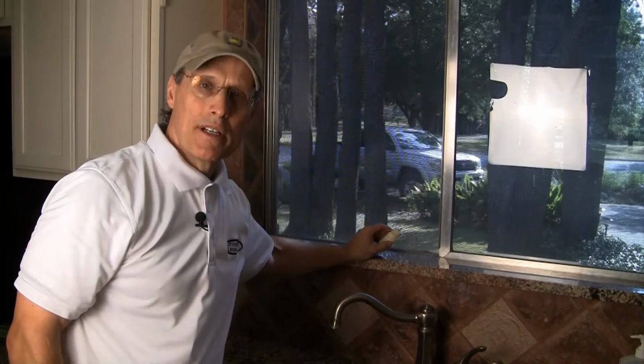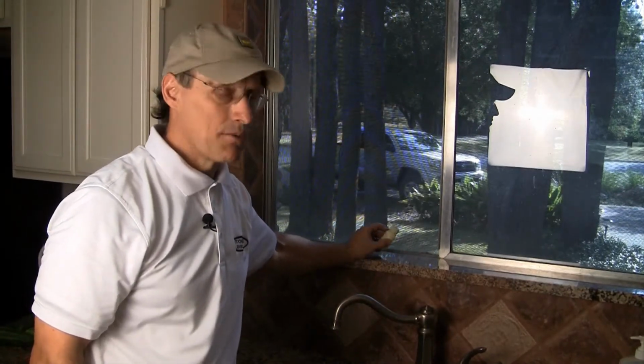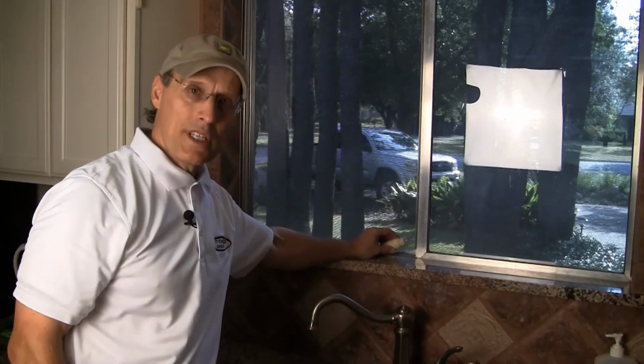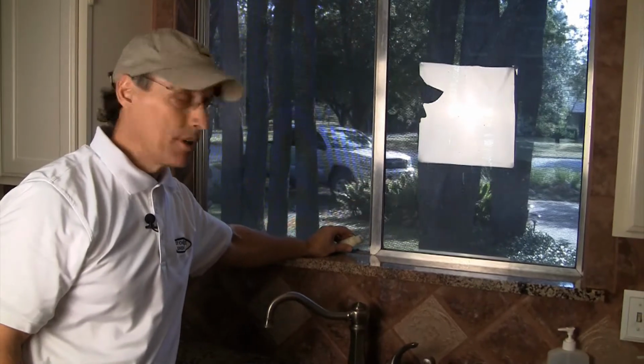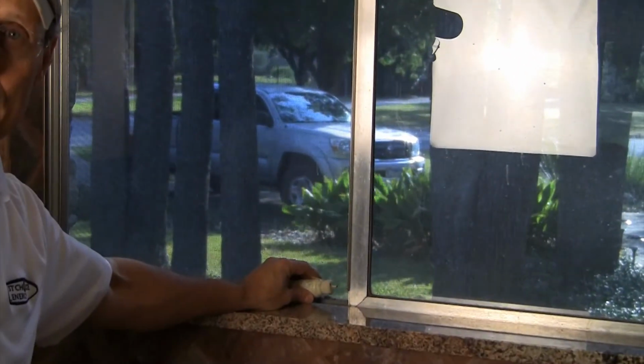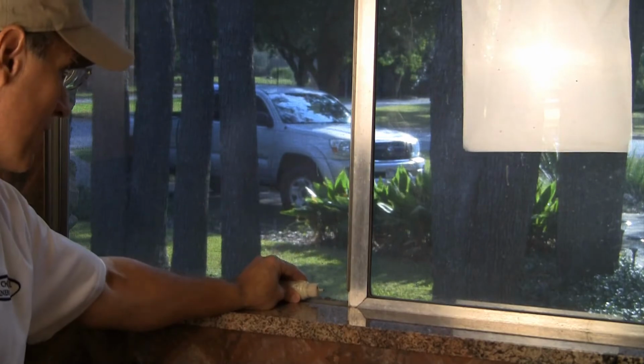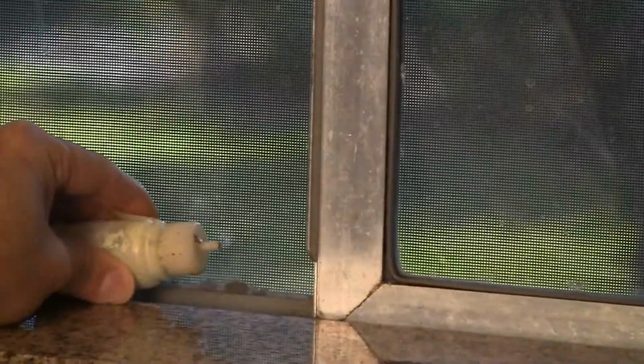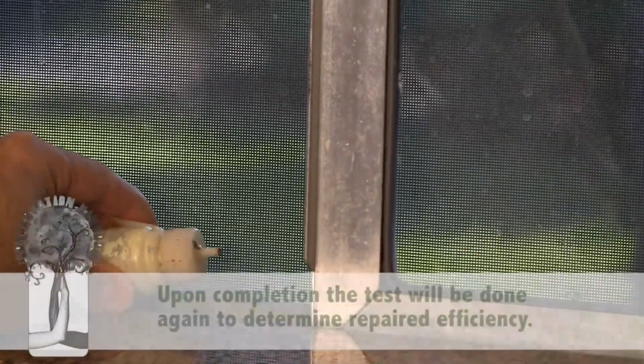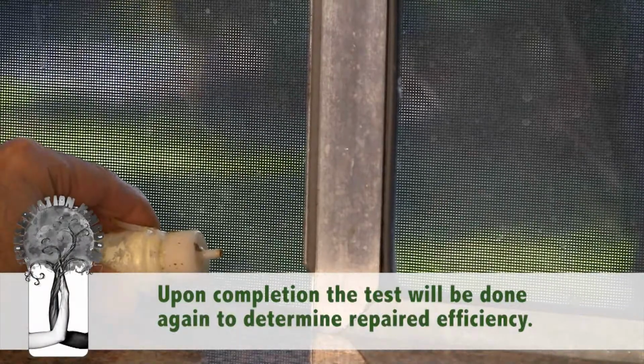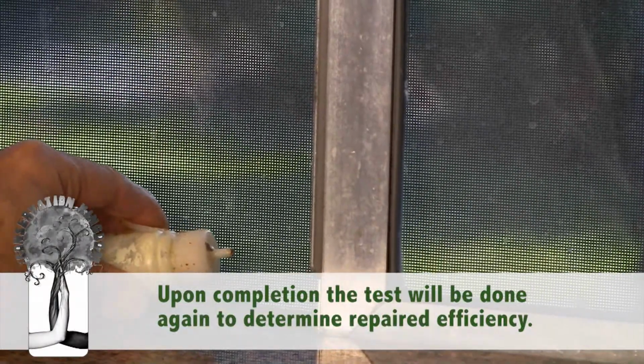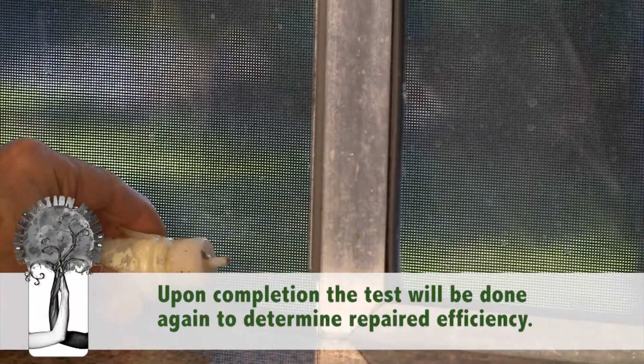Another common area of air infiltration into a house is around leaky windows. And so you'll see these are single pane aluminum frame windows, about 30 years old, 40 years old. And you can see if I puff smoke, I'm getting a pretty high leakage rate around this window and into the house. So leaky windows are another common source of air infiltration into a house.